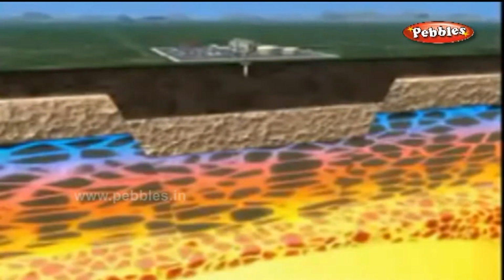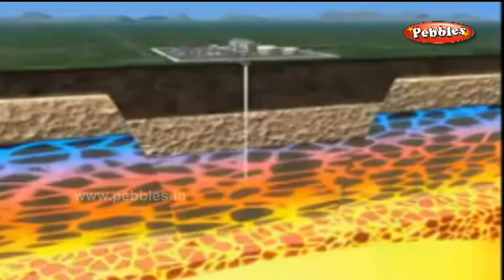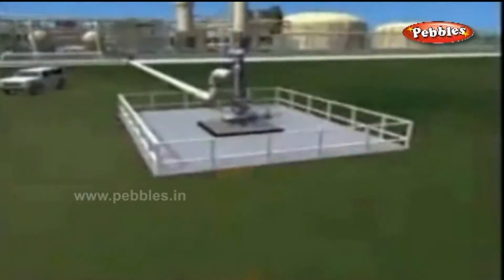To reach the superheated fluid, wells are drilled 5,000 to 10,000 feet below the surface of the Earth. These wells, called production wells, bring the superheated fluid to the Earth's surface, where it can be used to generate electricity for homes and businesses. Under its own pressure, superheated fluid from the geothermal resource flows naturally to the surface through production wells. As the liquid flows toward the surface, the pressure decreases, causing a small portion of the fluid still within the well to separate or flash into steam.